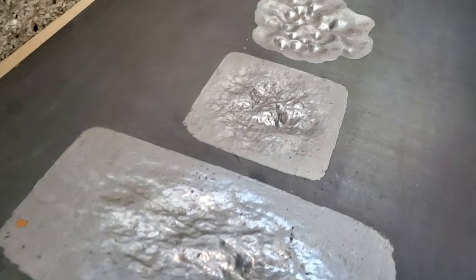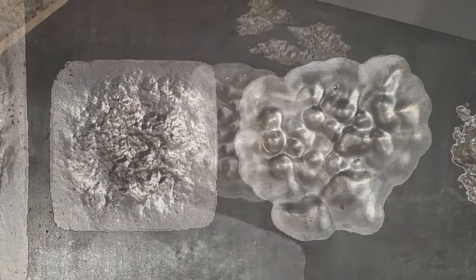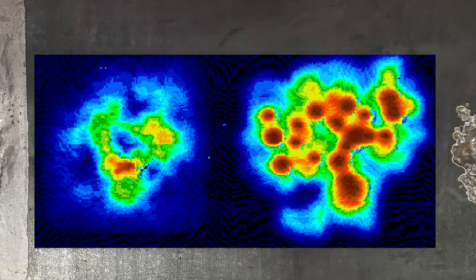And that's basically it. And if I take this image and digitally superimpose it on the plate, you can see that it matches really well. That's HydroFORM on a Sonatest Veo.